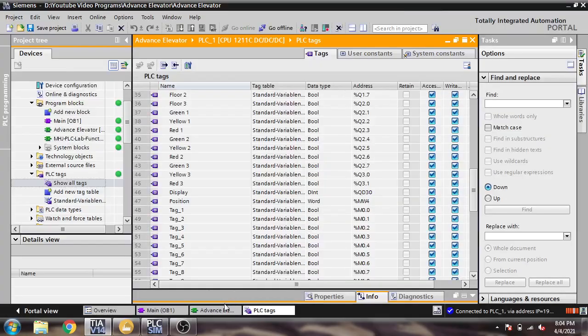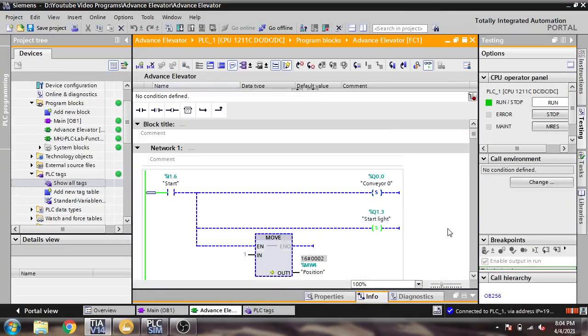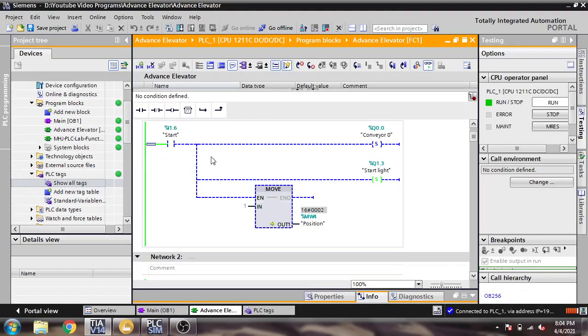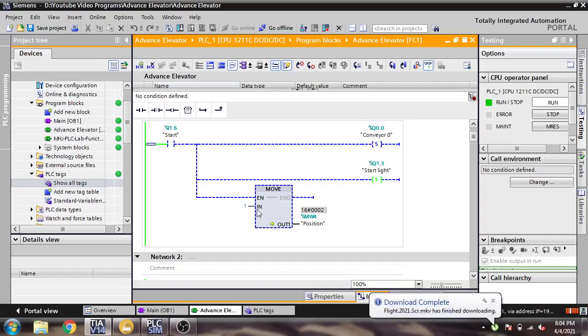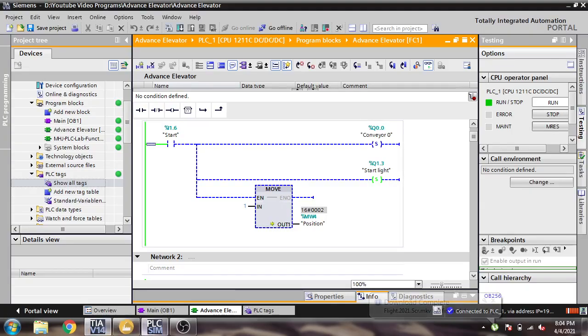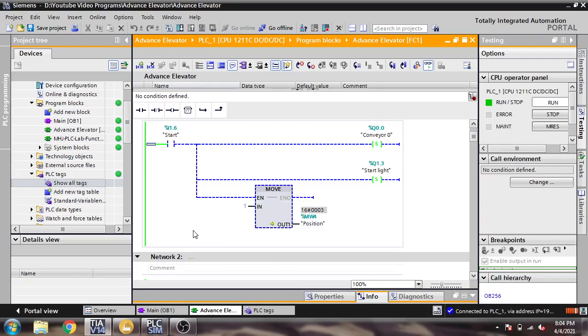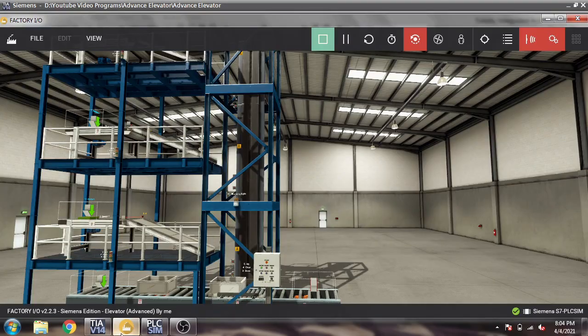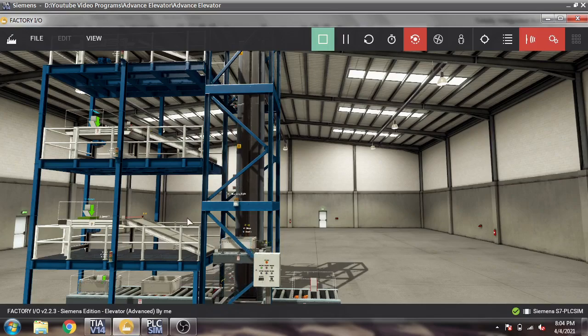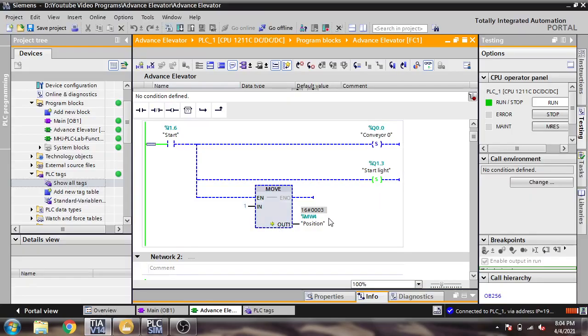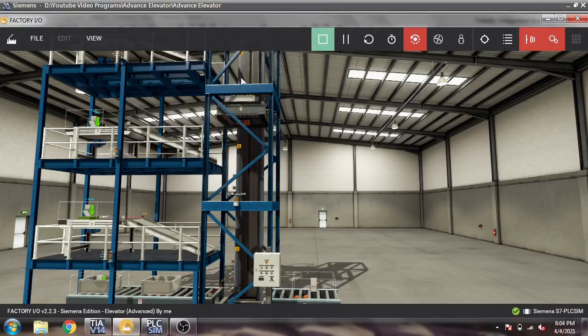At position zero, first we push the Start button. It will start Conveyor Zero, turn on the start light, and move the value 1 to our position variable — I am using an internal memory to track which position we need to stop the conveyor at. It will first go to position three.